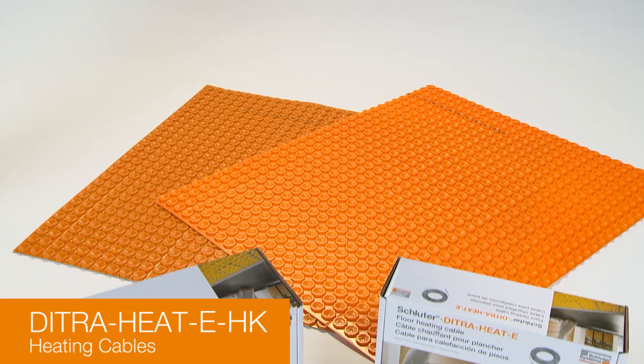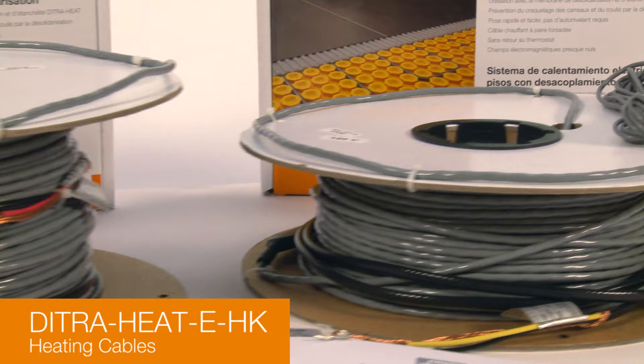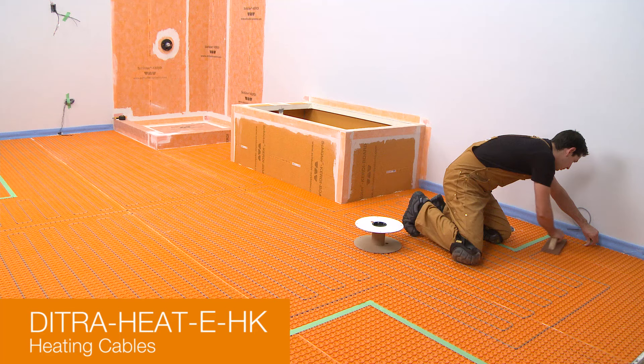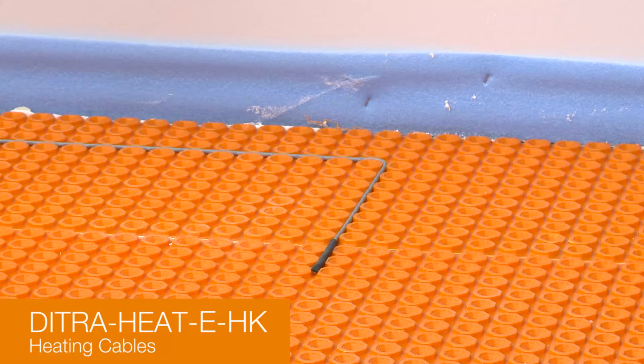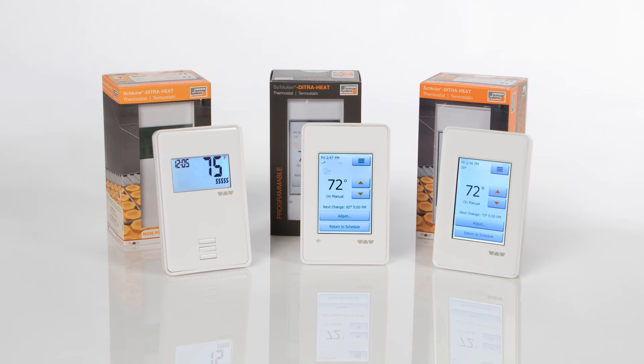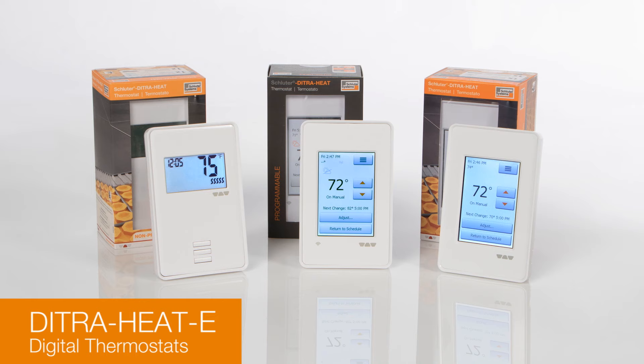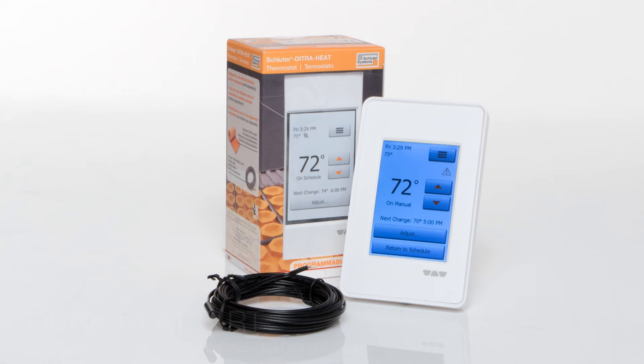DITRA-HEAT EHK are twisted pair heating cables specifically designed for integration into the DITRA-HEAT uncoupling membrane. They are available in both 120-volt and 240-volt versions and a range of lengths. The cables can be installed without returning to the thermostat and produce virtually zero electromagnetic field. DITRA-HEAT e-thermostats are digital thermostats with remote floor temperature sensors that control the heating cable's operation. They feature built-in ground fault circuit interrupters of the class A type and support both 120-volt and 240-volt cables.